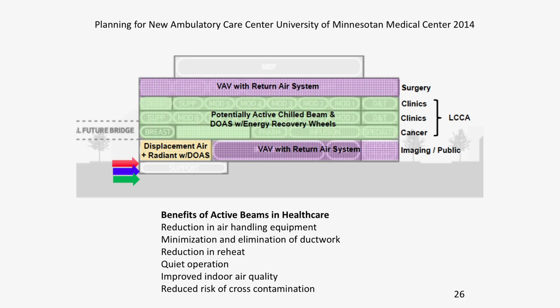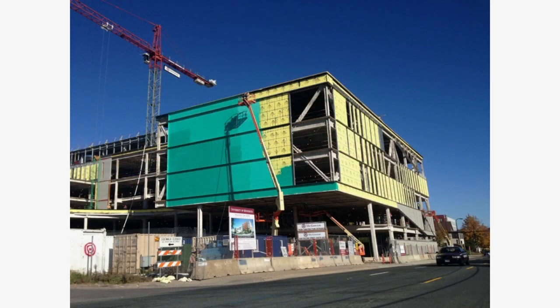In the next slide we see a building going up, and the value of the chill beam is you get a good exterior wall, painted in this case with an elastomeric chemical that seals the wall to keep the humidity out. We need to keep the humidity out in most instances, but if you want to save energy using chill beams, this is what you have to do. And it's a good thing, because keeping that humidity out really reduces the infiltration of moisture and mold.